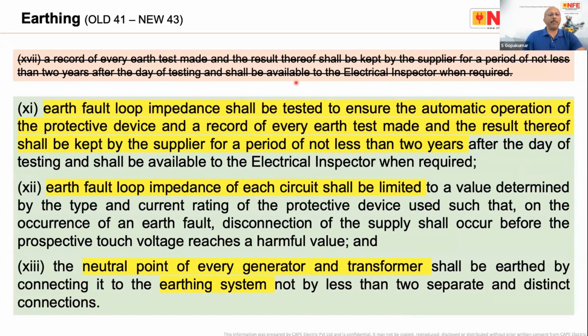With respect to automatic disconnection of supply, here you can see regulation 43, sub-regulation 11. It says earth fault loop impedance shall be tested to ensure automatic disconnection of the protective device. This regulation 11 is talking about the supplier, that means the DISCOM, the electricity distribution company. They are supposed to measure the fault loop impedance at the point of commencement of supply, and keep a record of the result for a certain time for the electrical inspector to verify. Similarly, regulation 12 says the earth fault loop impedance of each circuit shall be limited to a value determined by the type. Basically, regulation 12 is talking about testing of fault loop impedance for every circuit. That means the user, the house owner, should do this particular testing.